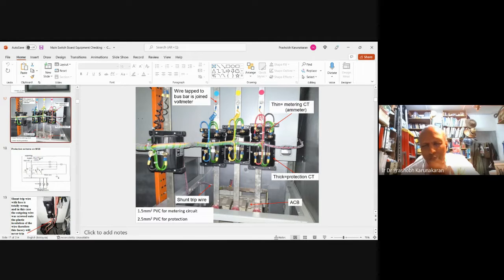Because in the main switchboard you have a capacitor bank. That's the biggest difference between a main switchboard and a DB: they have a capacitor bank. They have a lot of capacitors to balance out the coils, because your factory mostly uses motors, which use coils. The capacitor bank balances out the coils.